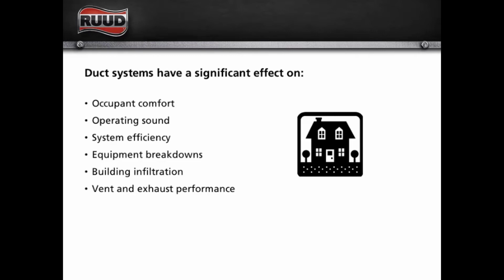Improper airflow obviously can affect efficiency, especially with ECM blowers. So with a constant torque and a constant volume, right, or what is typically referred to as an X13 motor and/or a variable speed motor, the harder those blowers work, the more energy they use. So if you're going from a situation where you've got a permanent split capacitor, or a PSC motor, in an air handler, and you change that out with a constant volume motor, if your ductwork is undersized, that constant torque or that constant volume is going to use more energy than the PSC that you took out.